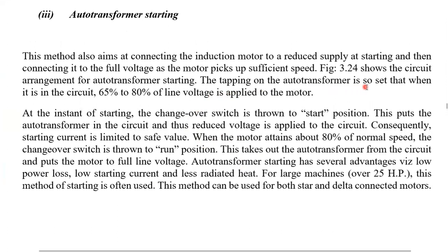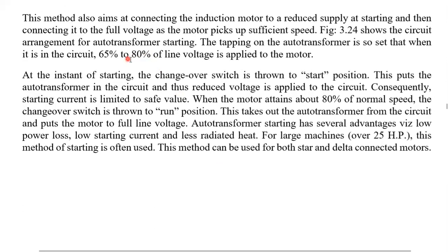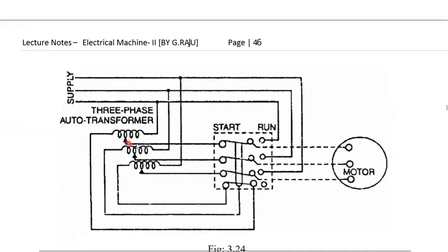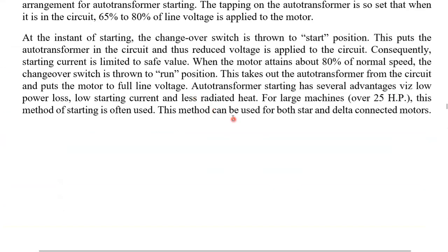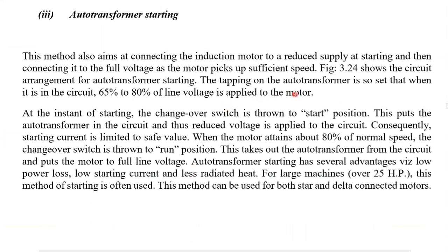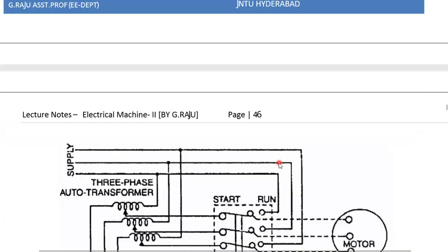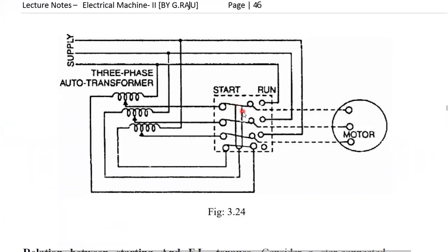Here, the tappings of the transformer are set so that when it is in the circuit, 65% to 80% of the line voltage is applied to the motor. So by changing the tappings of this transformer, we apply this reduced voltage of 65 to 80% of the line voltage to the motor at the time of starting. At the instant of starting, the changeover switch is thrown to the start position. So we have to close the switch at starting like this and change over the switch to the start position. Understood?